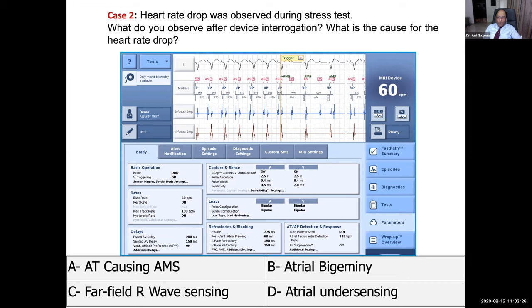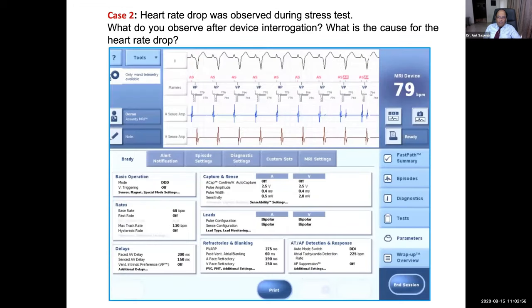We can see the automatic mode switch is on, programmed to DDI, and the tachycardia detection is set at 225. So whenever the heart rate reaches around 225, the patient will go into automatic mode switch into DDI mode. This is very important to diagnose, and even more important to prevent, because we can prevent this kind of thing from happening if we take adequate care at the time of implantation. So that's how it looks in real time.